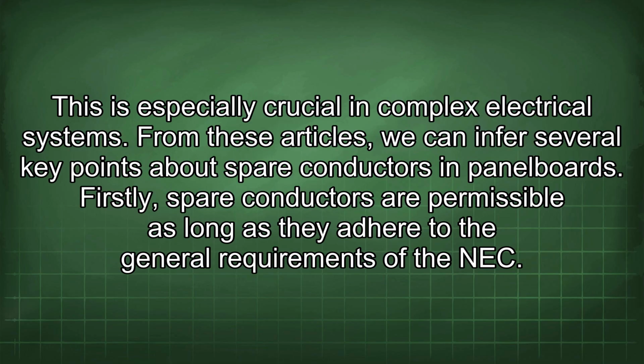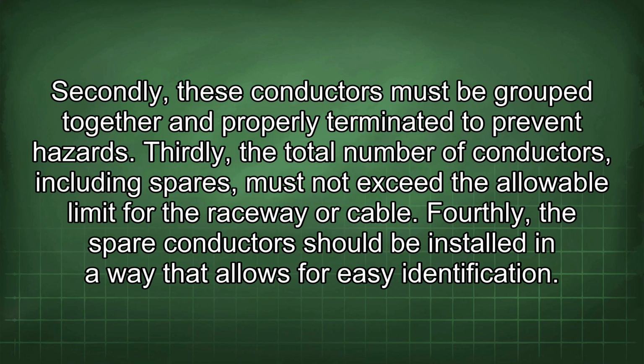From these articles, we can infer several key points about spare conductors in panel boards. Firstly, spare conductors are permissible as long as they adhere to the general requirements of the NEC. Secondly, these conductors must be grouped together and properly terminated to prevent hazards. Thirdly, the total number of conductors, including spares, must not exceed the allowable limit for the raceway or cable. Fourthly, the spare conductors should be installed in a way that allows for easy identification.